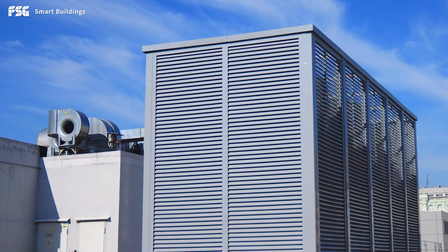And of course, this is more of a sophisticated method of talking to these units. It's only available on newer, what I would call smart, rooftop units with an onboard processor. And there are literally hundreds of data points available that we can read from those units through a BACnet native integration process like that. And then there's quite a few points that are available to write to as well, so you can do both read and write.